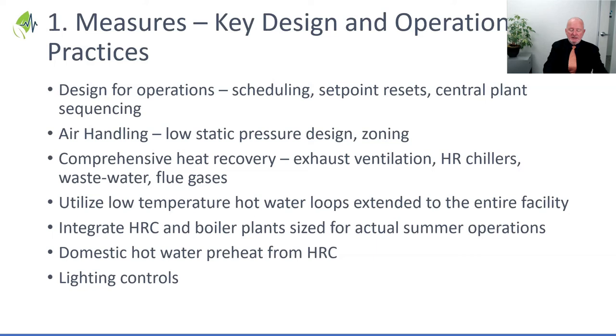Always preheating domestic hot water from the heat recovery chiller - using that recovered heat to preheat your domestic hot water is a significant load. And especially at Humber River, those lighting metrics we saw - good lighting controls - it's dramatic just how low the lighting electricity can be. It's the lowest of the group, and it still has largely fluorescent lighting.